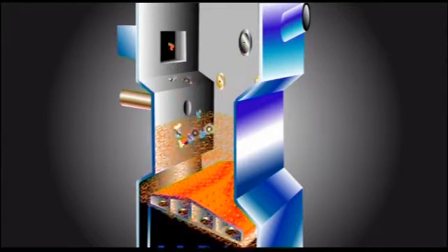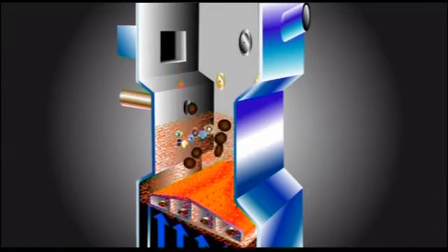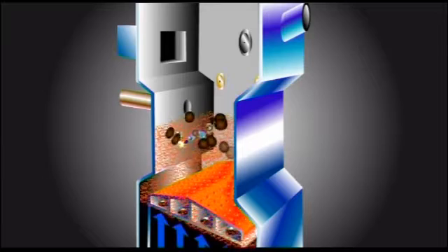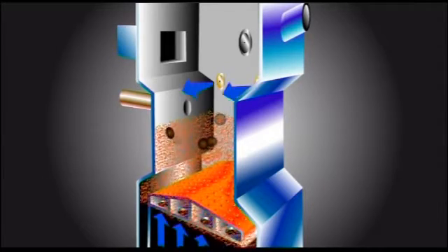The temperature in the furnace remains constant thanks to the calorific content of the waste. The sludge is introduced to the furnace by four sidewalls. Secondary air is blasted in above the sand bed to ensure optimal incineration.